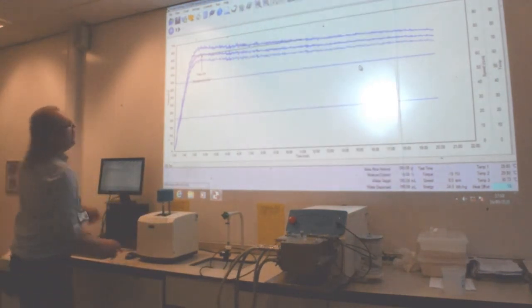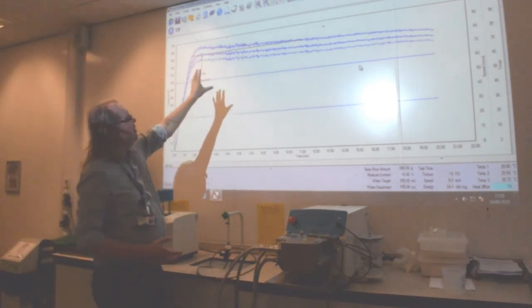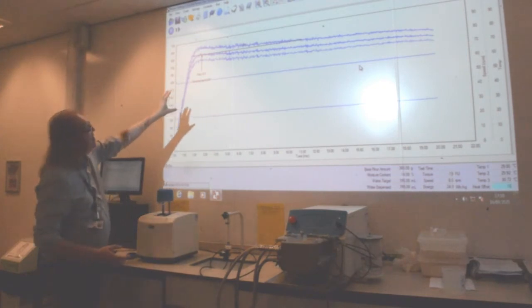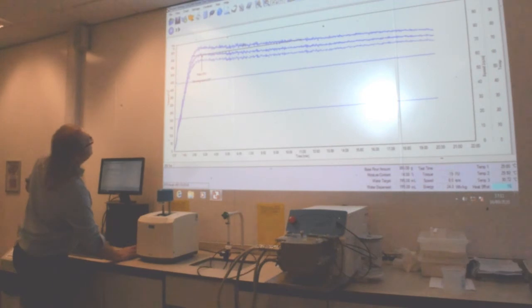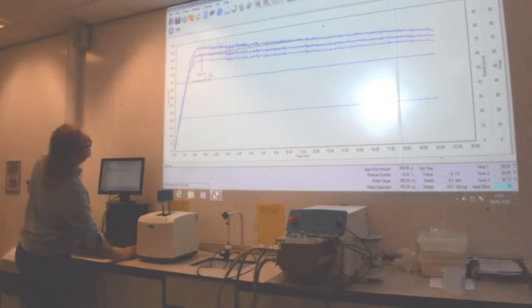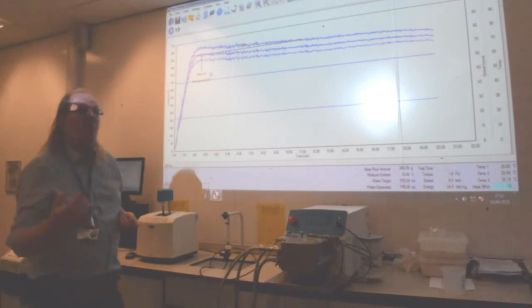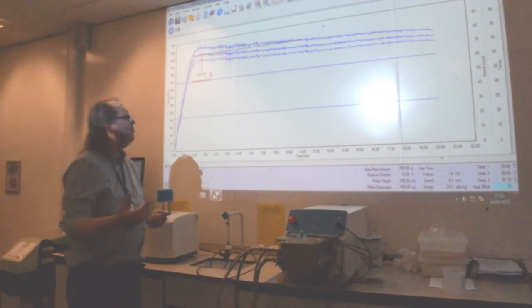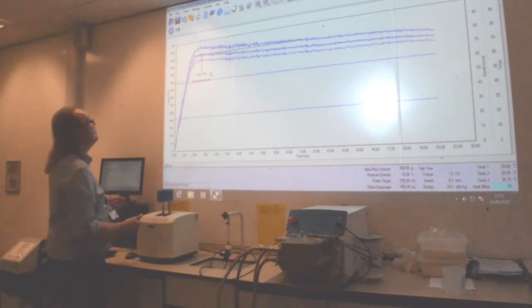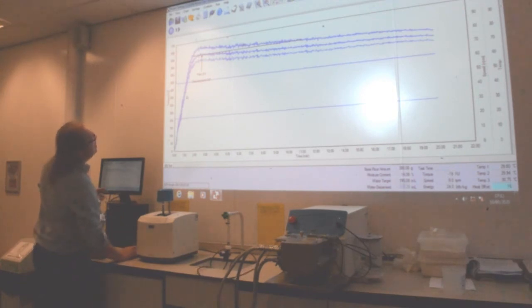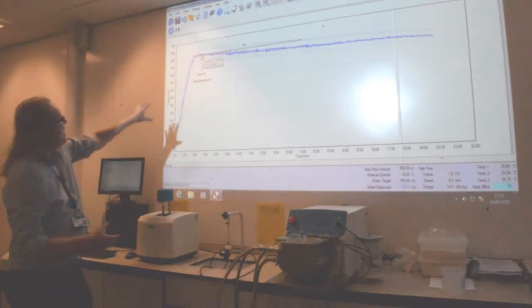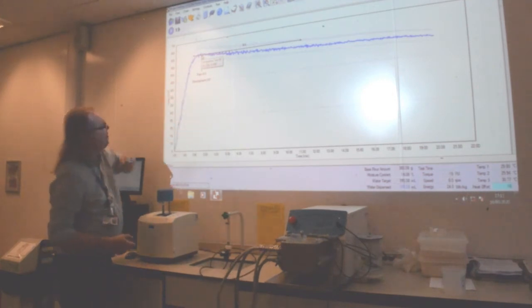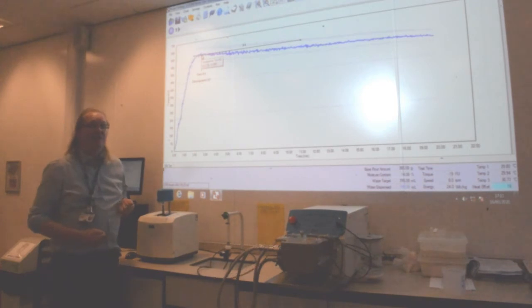The other thing that's really useful to look at is the actual screen where we can see the trace. What we have is indicated where the peak is. This particular sample is peaking at 610. Remember we want it to peak at 600 for accurate results. It would then also give us the development time, so how long did it take of mixing to get to that peak time. In this case the development was 2 minutes 57 seconds, so a very quick development time.